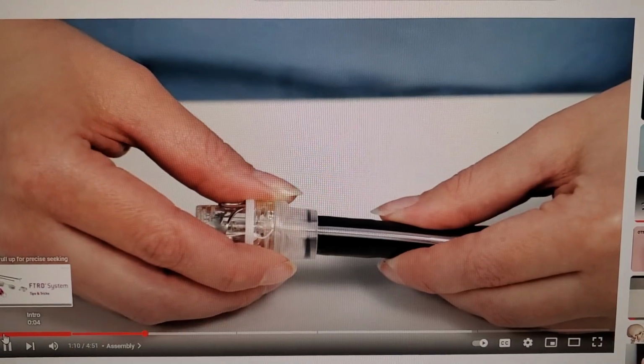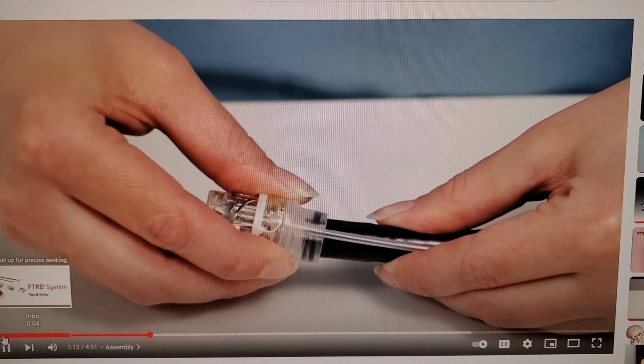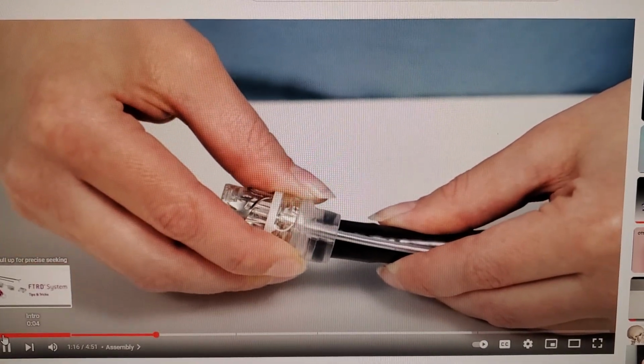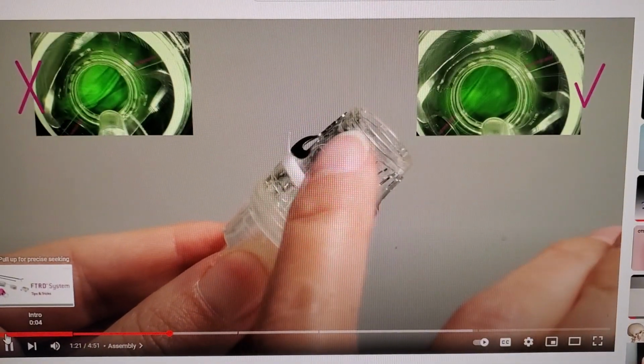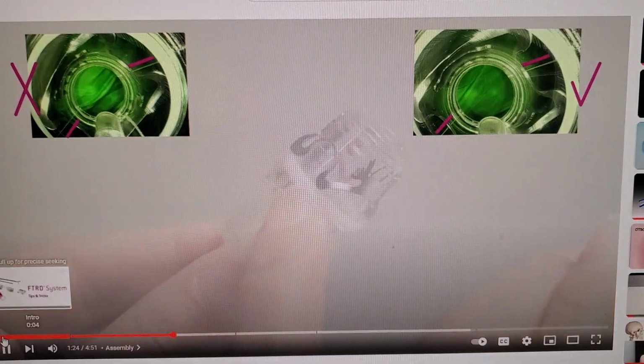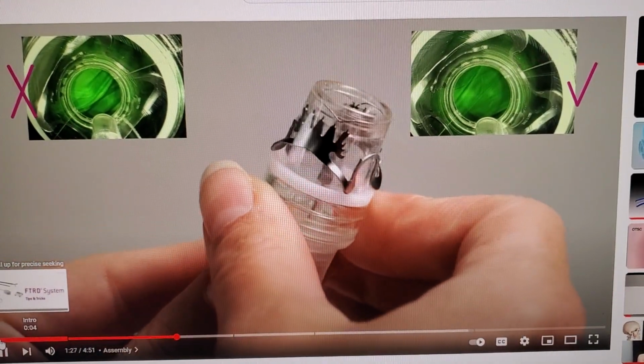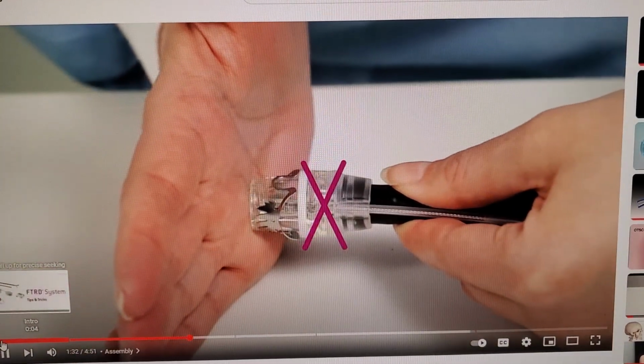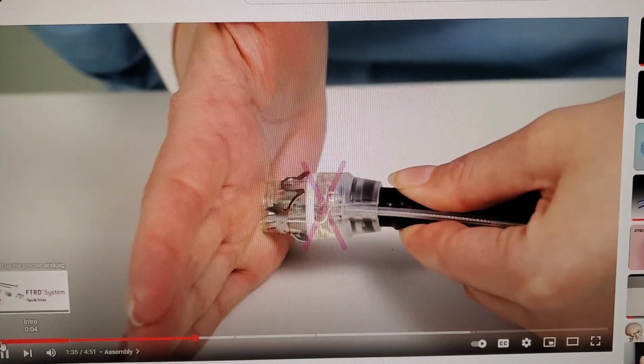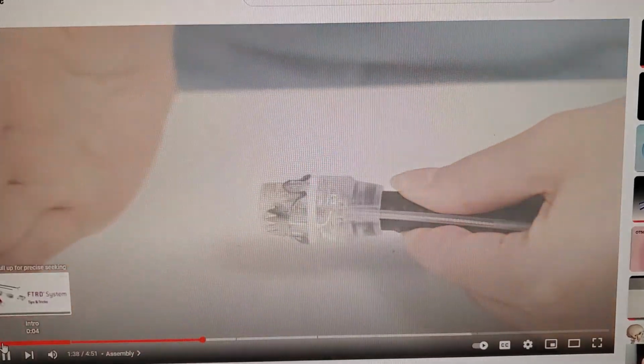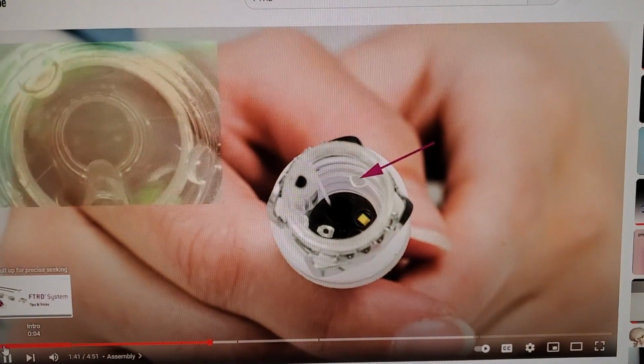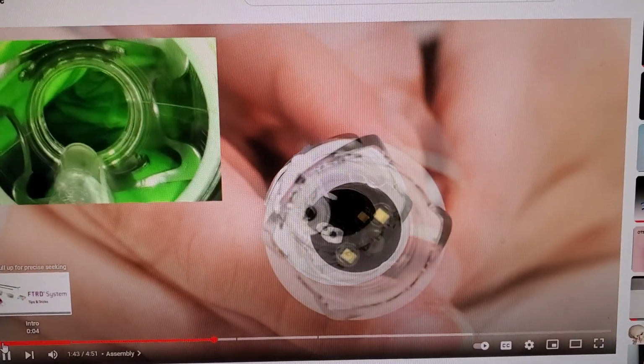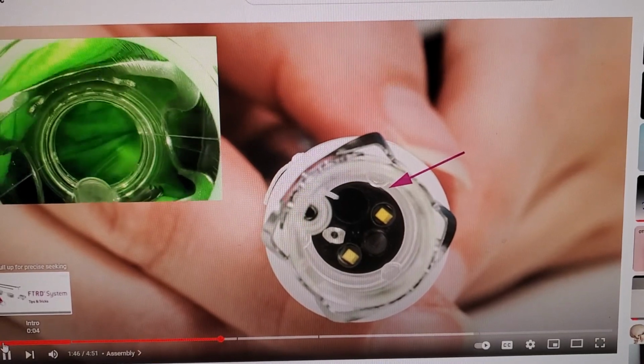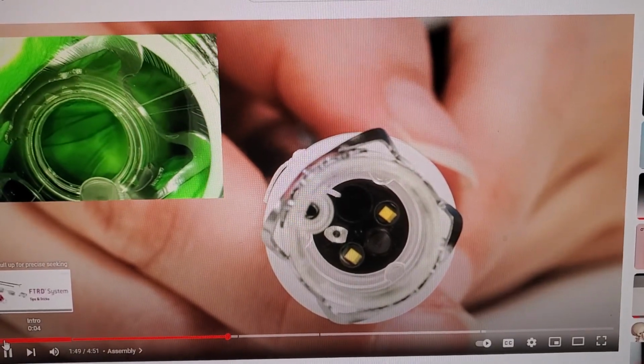Slide the cap further onto the endoscope shaft with slight lateral tilting movements, which also protects the endoscope sleeve. During assembly, it must be ensured that the clip remains correctly positioned on the application cap. It must not be twisted or caught by the thread. The cap should not be pressed against the hand or table during assembly, as this could damage the cap. The cap must be pushed onto the endoscope until the endoscope tip abuts against the endoscope stoppers in the cap and are no longer to be seen in the endoscopic image.